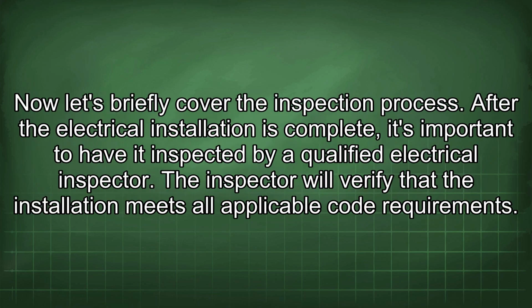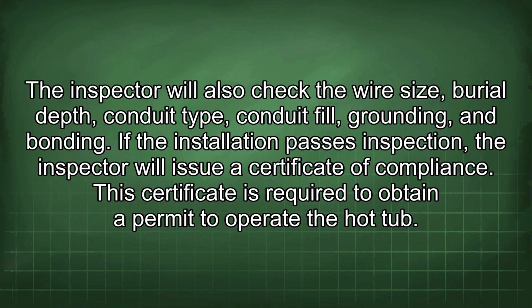Now let's briefly cover the inspection process. After the electrical installation is complete, it's important to have it inspected by a qualified electrical inspector. The inspector will verify that the installation meets all applicable code requirements. The inspector will also check the wire size, burial depth, conduit type, conduit fill, grounding, and bonding.